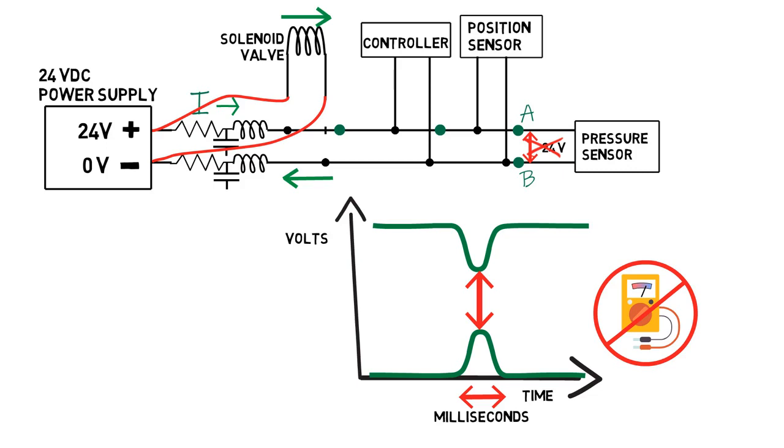Regardless of which method you use, remember that you need to keep the plus and minus wiring of each section separate. It doesn't really help if you separate the plus wiring, but all the minus wiring still goes to the same terminal strip before going to the power supply.